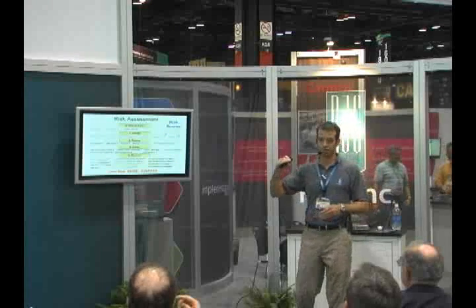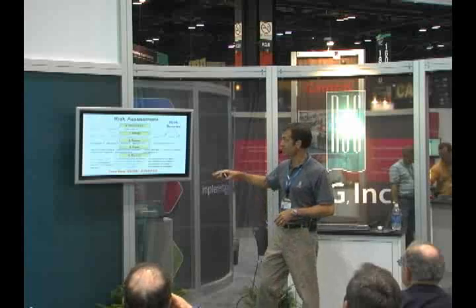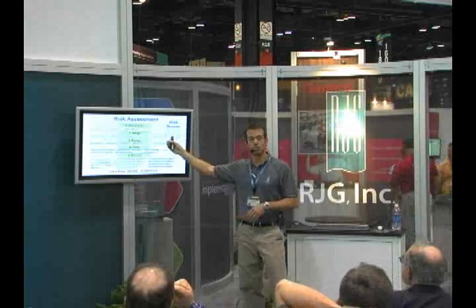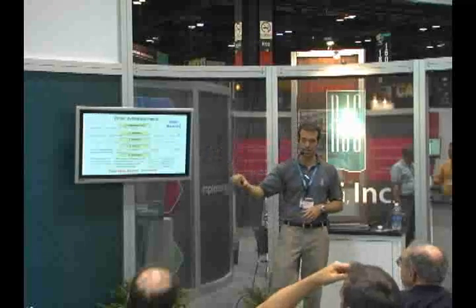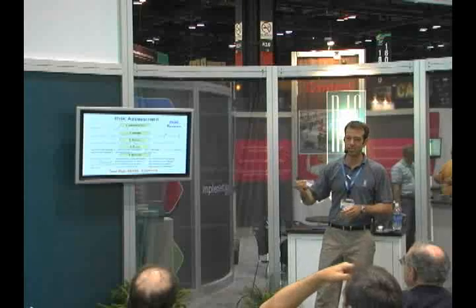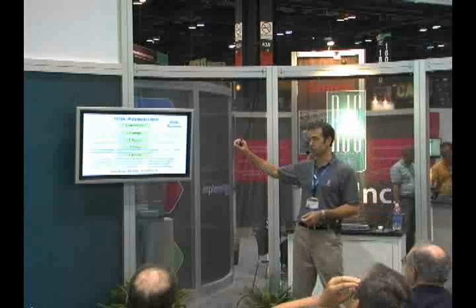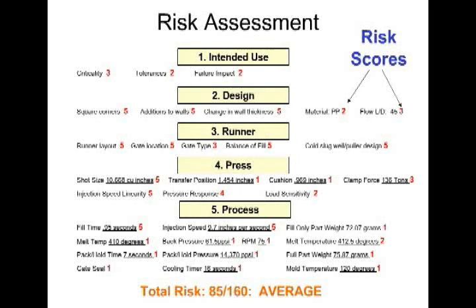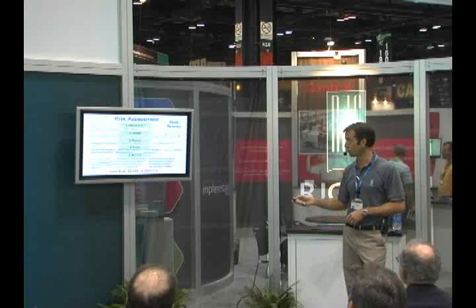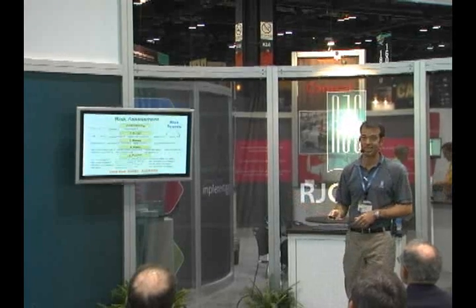One of the unique things that comes out of this systematic approach to validation is we can take aspects of the design phase — the IQ, the OQ, the PQ — and identify risks associated with all of that selection process based on the intended use of our part. So my tool design, wall thickness considerations, the material I'm molding, down into the process and the significance of pressure response on my molding machine — all of those things can be assigned a risk category. At the end, you have a good understanding of what areas you need to focus on to ensure you end up with a validated process that's easier and more efficient to manage.